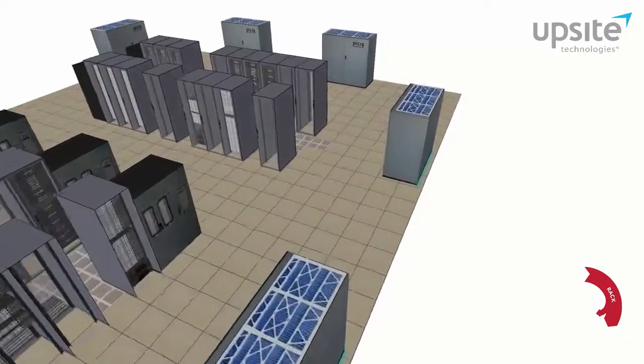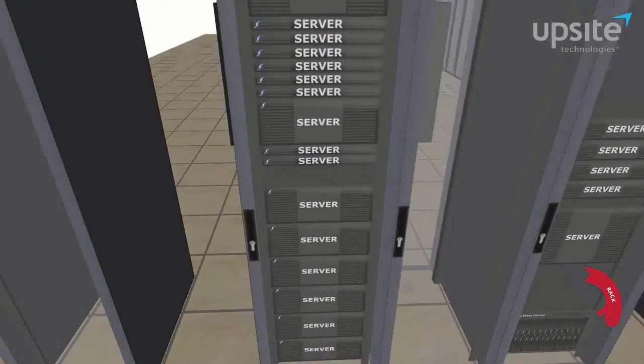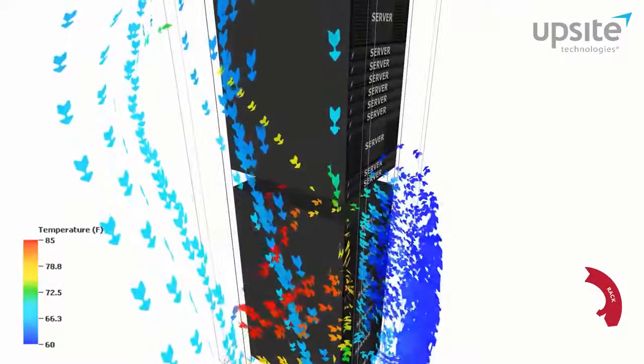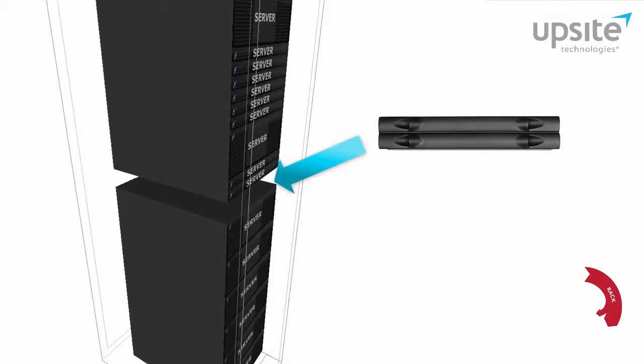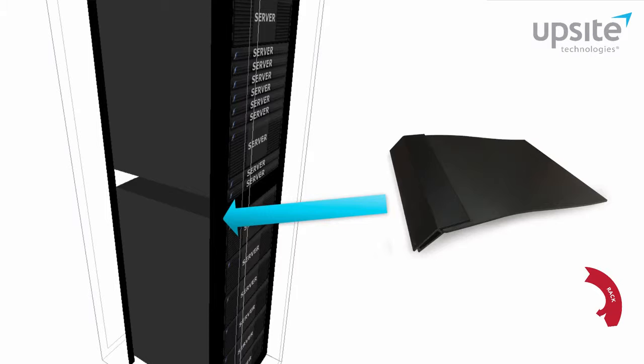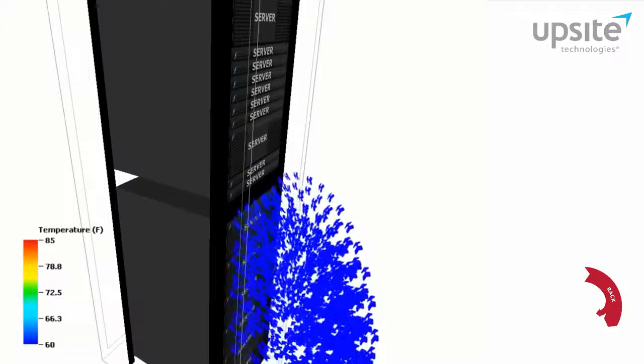First, we address the rack. Sealing all open gaps in the rack prevents harmful exhaust air recirculation and helps protect the reliability and longevity of the IT equipment. By installing HotLock blanking panels in empty U spaces and installing the HotLock rack airflow management kit on the open sides of the rails, we obtain complete sealing at the face of the racks.